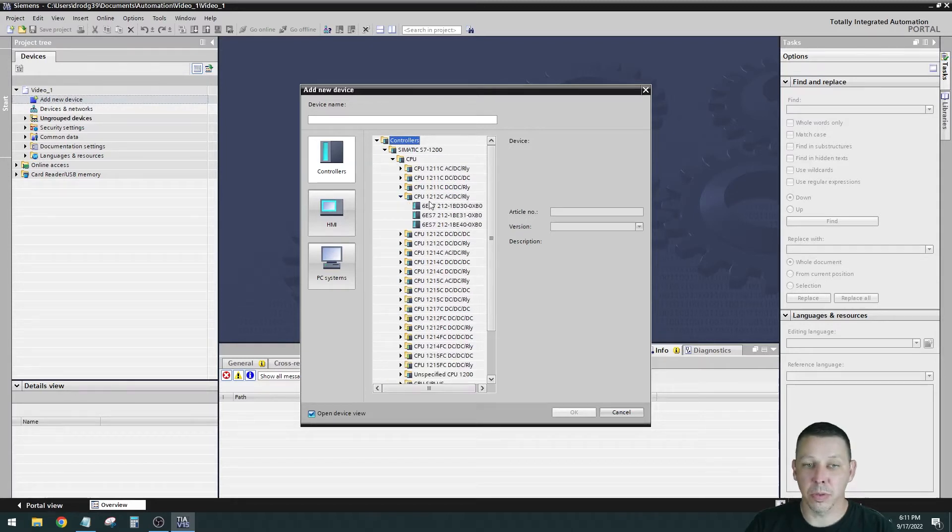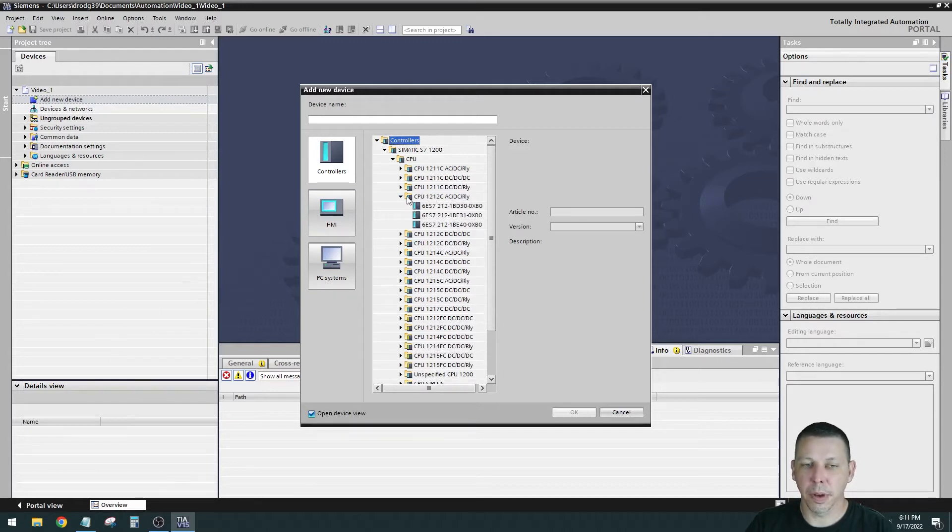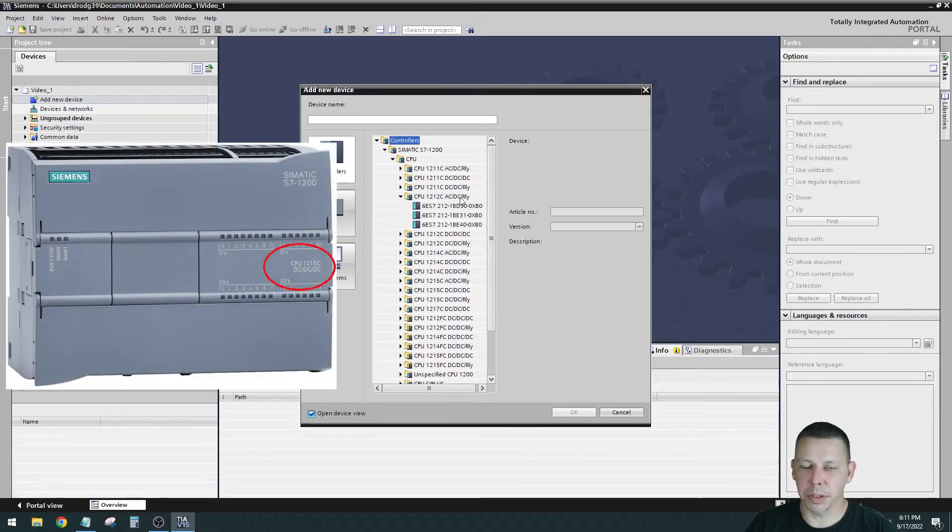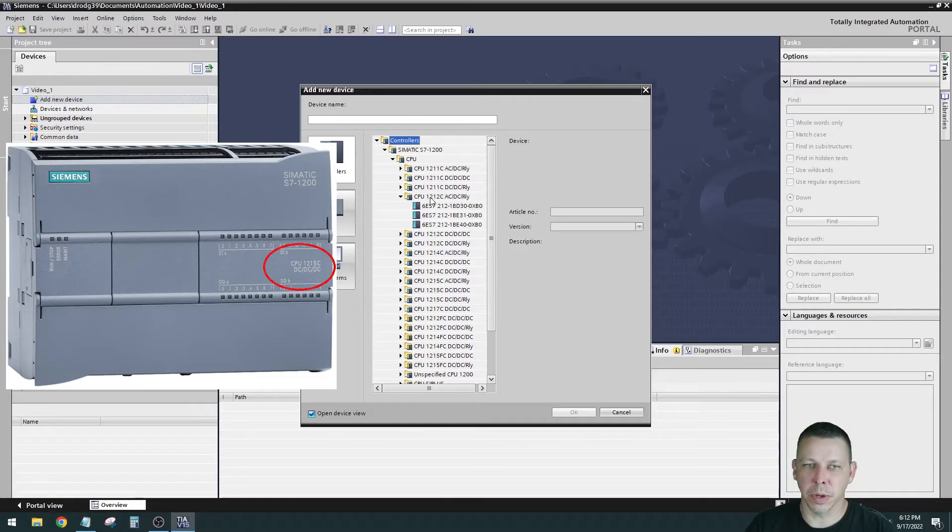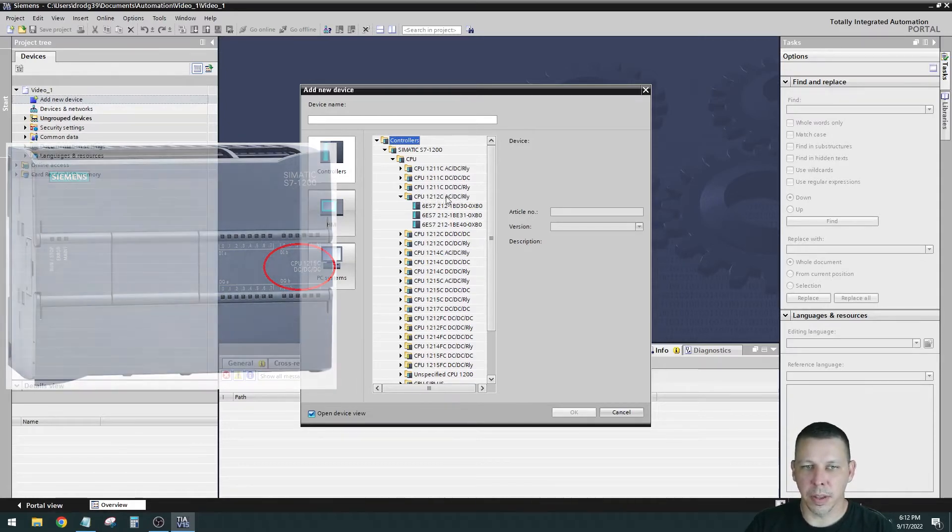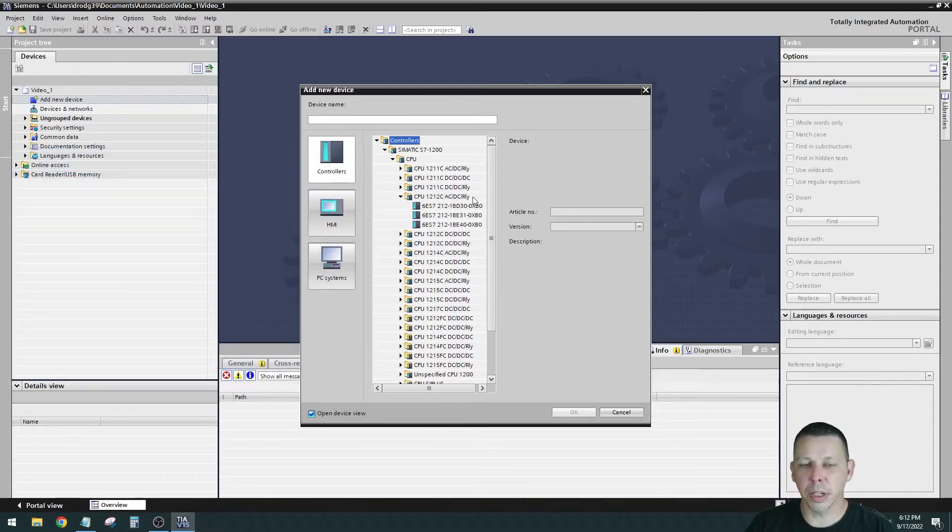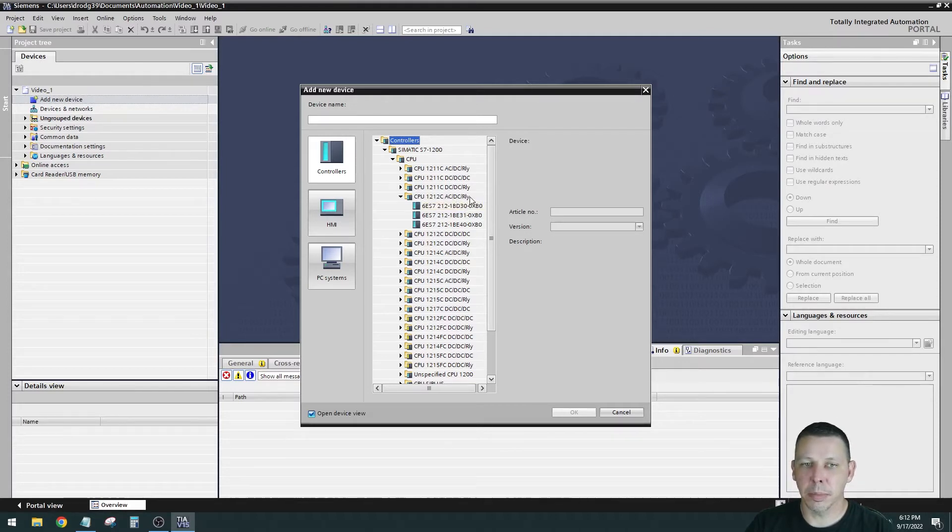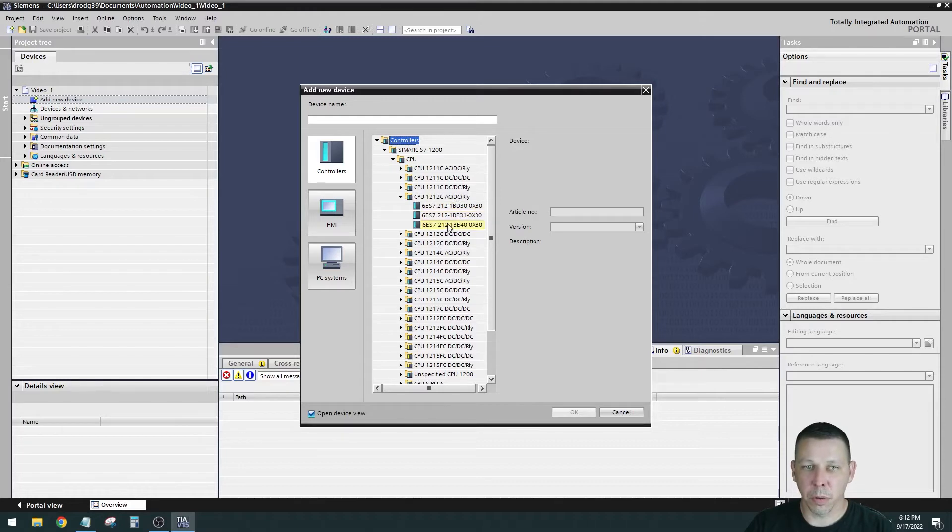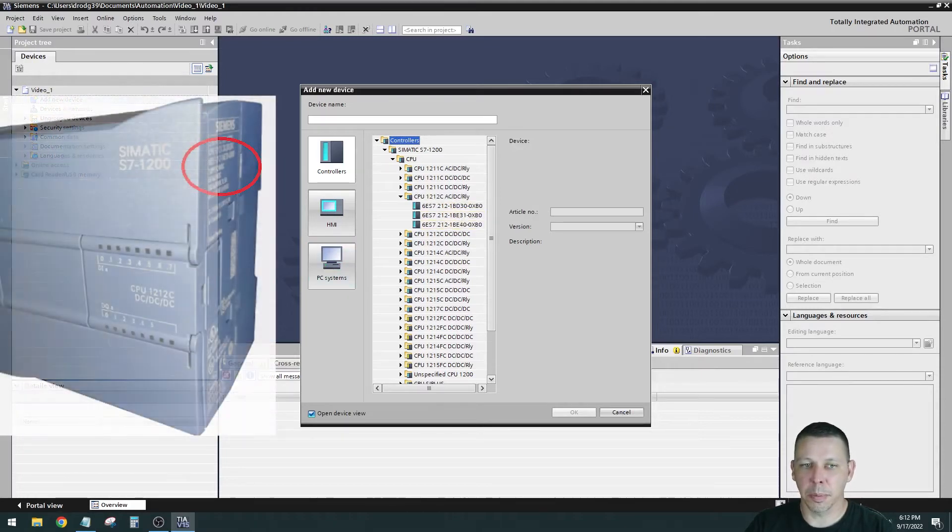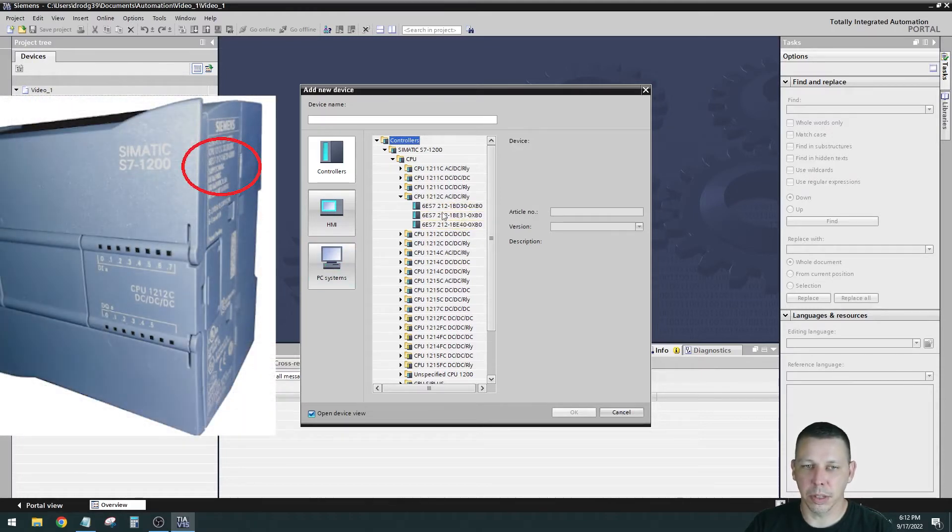I'll drop a picture in after I edit this video, but the front of an S7-1200 will show where you're going to find this information. It's on the front of the processor on the right hand side. It'll tell you 1212C and then AC-DC and relay. It's AC powered, has DC inputs and relay outputs. That's what that means.